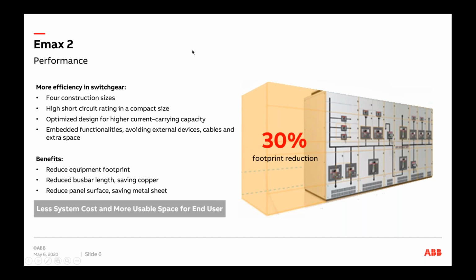Now, speaking of performance, we look at Emax 2 in mainly 4 construction sizes. So we have the E1.2, the 2.2, 4.2, and 6.2, right from a 1600 amp, which can be brought down to 250 amps, all the way up to 6300 amps. We have high short circuit ratings even in the smaller sizes. And then at the end of the day, they're optimized to carry higher current with a lower footprint. That is also in correlation with other conducting material within a switchboard, and then looking at temperature calculations separately. But the device itself allows us to reach certain footprint reductions. In terms of embedded functionalities, we have a lot of options, which I'll be discussing quite soon.